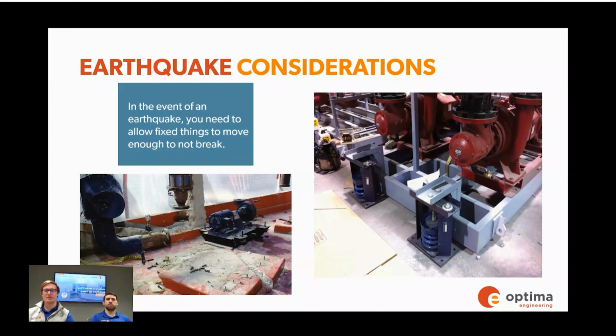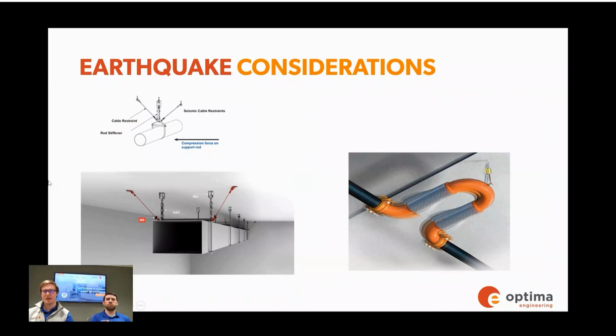In the bottom left, that piece of equipment, a pump, was bolted in place and fixed, and the earthquake movement really destroyed the system and threw everything around. On the right is a solution: providing a base and support for the pumps so they can shift and move along with the earthquake without destroying anything. Carrying out throughout the building, ductwork carrying air and piping carrying water can all be hung and supported from the building so that when the earthquake happens, it can move around without breaking the systems.